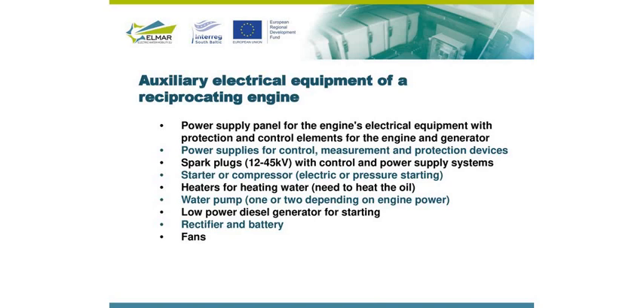The engine requires auxiliary electrical equipment. The engine needs a power supply panel for engine electrical equipment with protection and control elements for the engine and generator, power supplies for control, measurement and protection devices, spark plugs, high voltage with control and power supply system, and a starter or compressor; electric or pressure starting is possible. Heaters are needed to heat the water and the oil before start. It's not possible to start a cool engine because of possible damage.